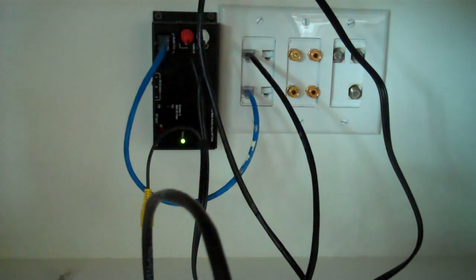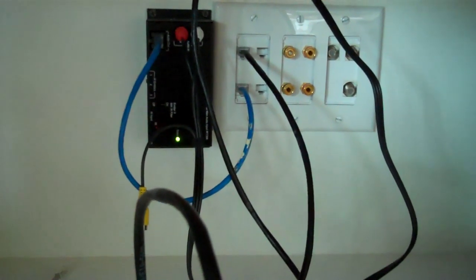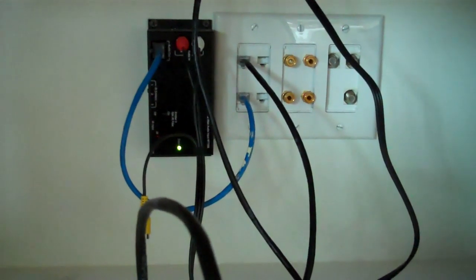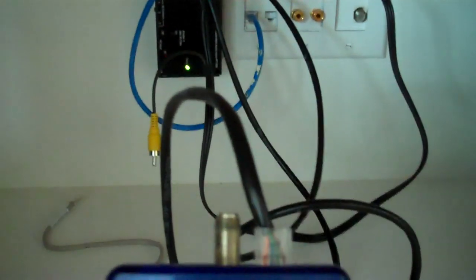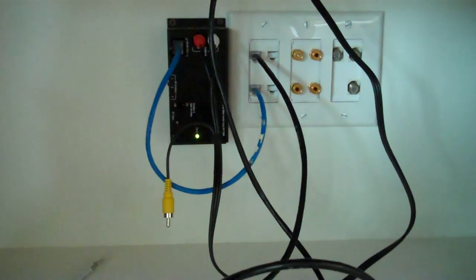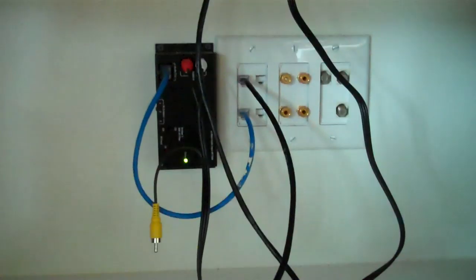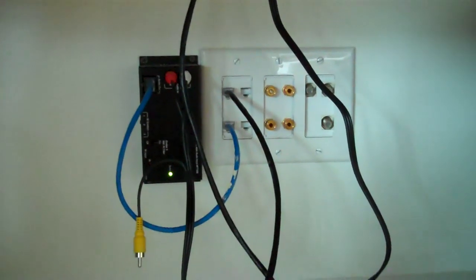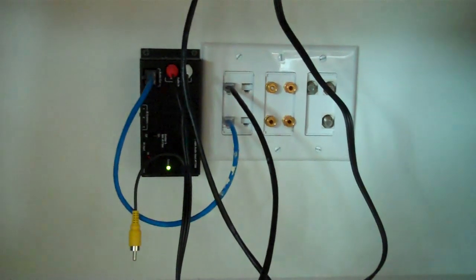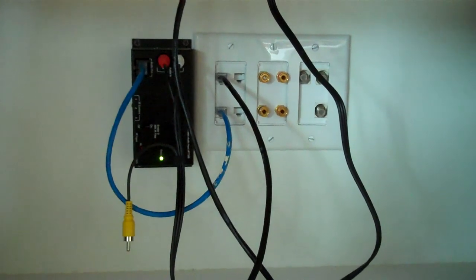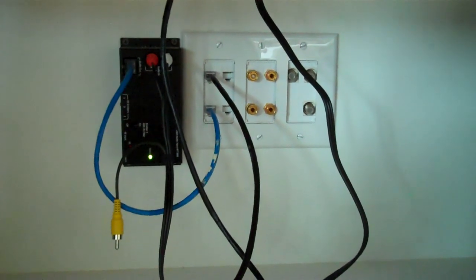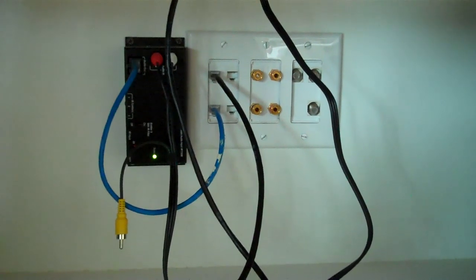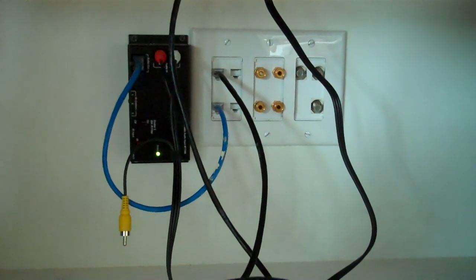Although it's plugged into the jack on the other end of the wire that's behind that plate, there's nothing plugged in. So we're tracing some things down. And this is another reason why labeling the wires and protecting the labels during construction is critical. Because if another trade paints over that label or rips that label off or the sheet rocker cuts that label off or what have you, then you have to do things like trace down and troubleshoot.